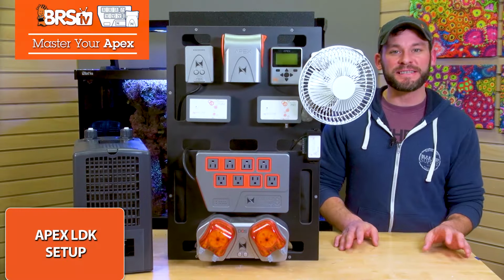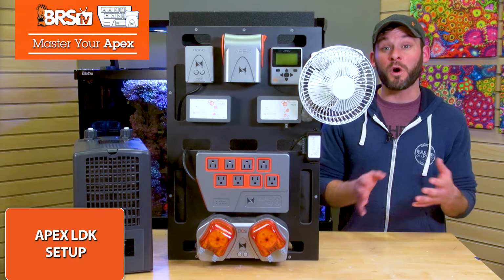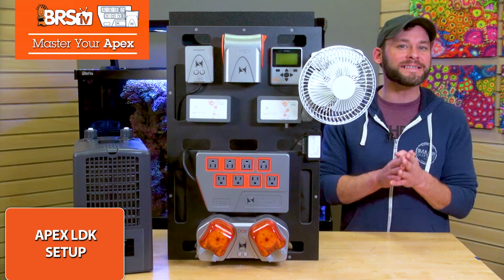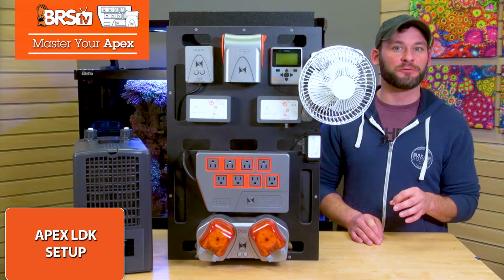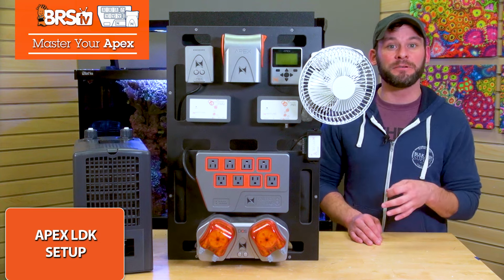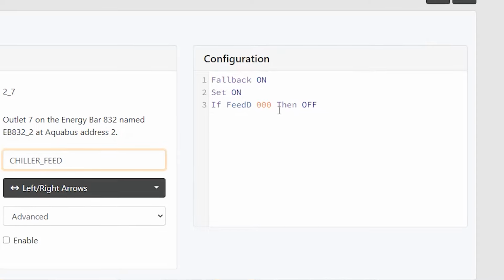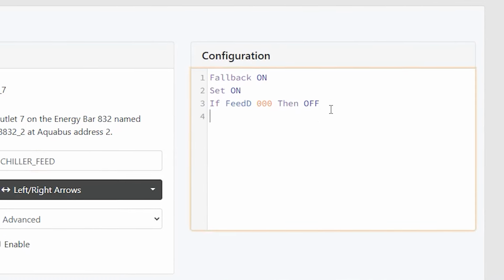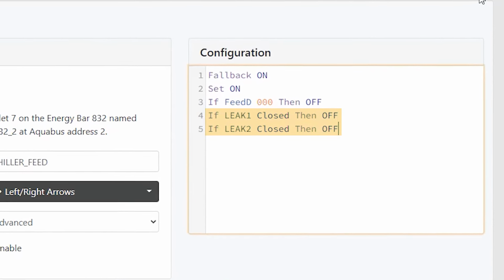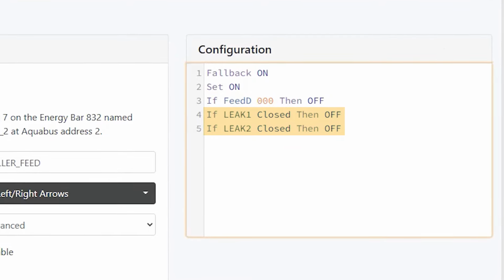So now you're set up to receive those email, text, and notifications when water hits the floor, but let's take it one step further and shut down the chiller feed pump in case a leak happens, which you can do by adding a new line to your feed pump outlet that says, if leak 1 closed, then off, and if leak 2 closed, then off, and you're set.